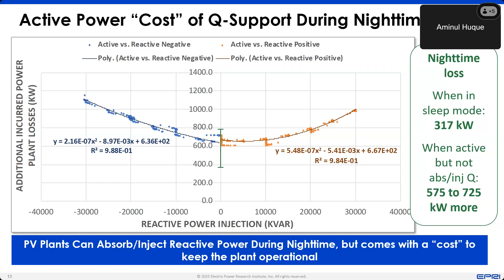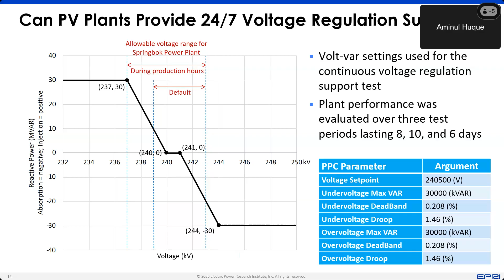Then once we have some level of conformance that yes, it can do it, the main thing we wanted to know was, can it do it seamlessly for several days, basically continuously? So we ran the test in three buckets: 8 days, 10 days, and 6 days. We configured the volt-VAR curve as shown in the picture. And again, this is a 240 kV target. Based on the utility requirement for target voltage, we configured the volt-VAR curve accordingly and wanted to observe how it does. That configuration was provided to the plant controller, and then we collected the data and analyzed it.